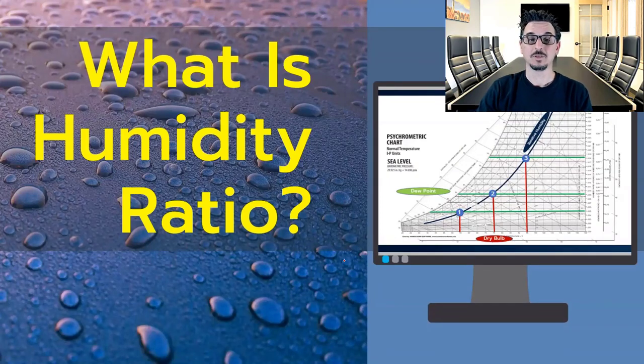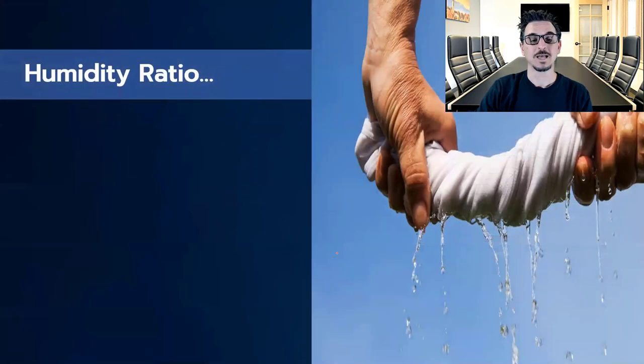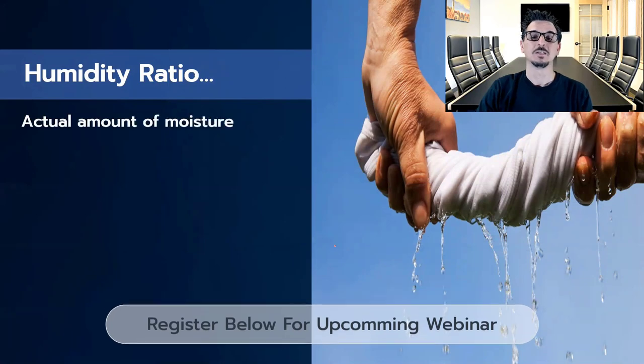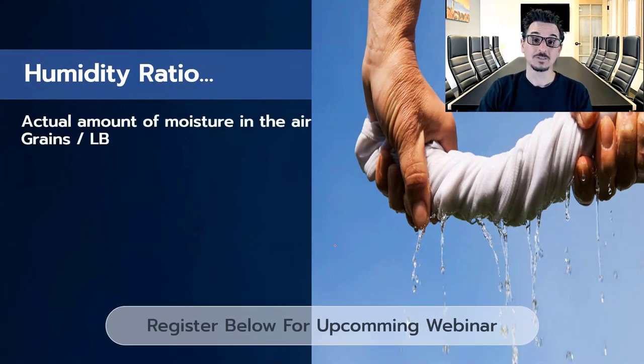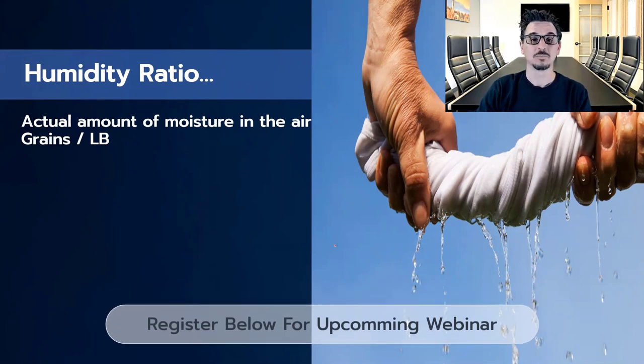What about humidity? When we talk about humidity on the psychrometric chart, we're looking at the humidity ratio. So what exactly is the humidity ratio? It's the actual amount of moisture in the air represented by grains per pound of air. It's also represented by pounds of water per pound of dry air.